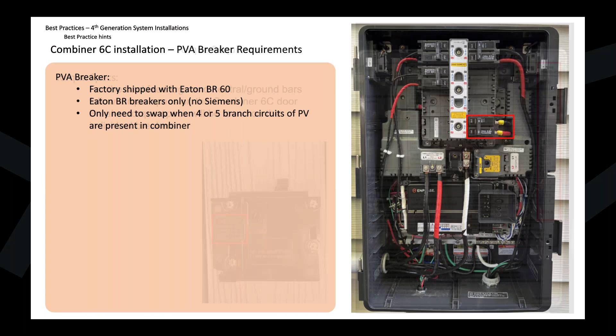Let's talk about torque requirements. I was talking to folks on our FAE team during White Gloves, and we're seeing this every week, unfortunately. Installers are putting the wires in and not torquing anything, whether it's the back feed lugs, the neutral bar, the ground bars, or even the breakers themselves. Those loose wires are creating thermal events, and we all know what happens when thermal events happen within the combiner: heat builds up, potential for arc, and worst case, fire.